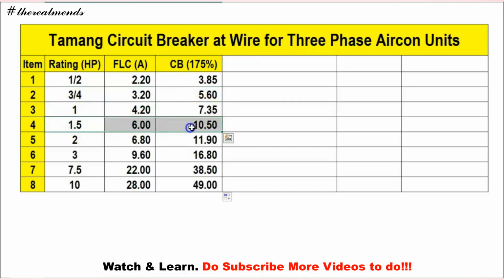Pag 1.5, 10.50. Pag 2 HP, 11.9. Pag 3, 16.80. Pag 7.5, 38.50. Pag 10, 49 amperes. So after that, ito yung ating na-compute na circuit breaker capacity. So i-check natin kung ano yung available sizes sa code.